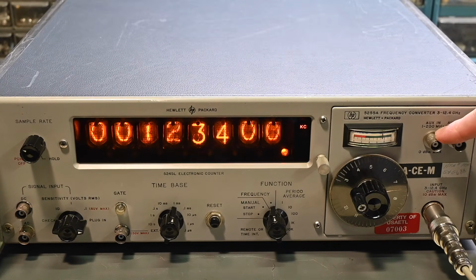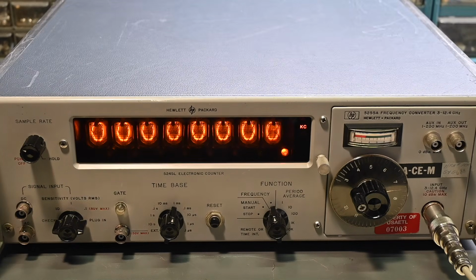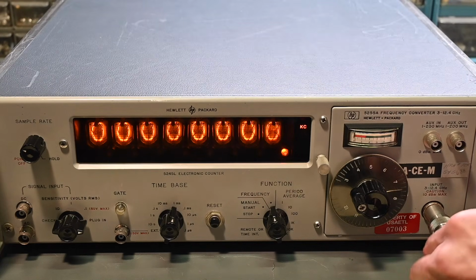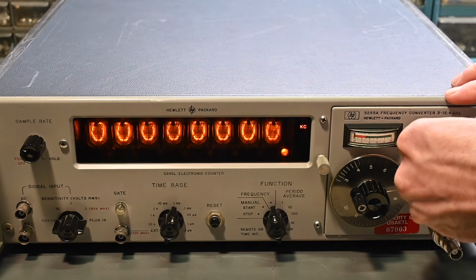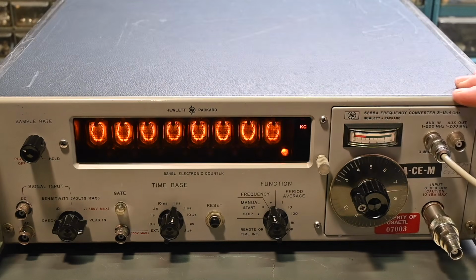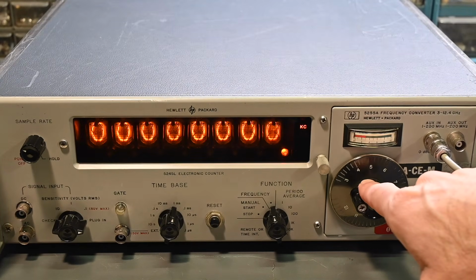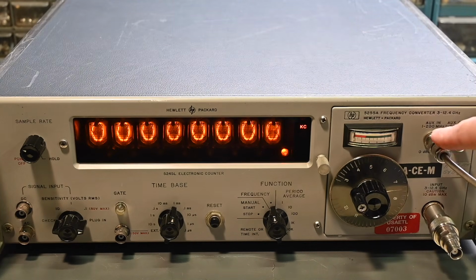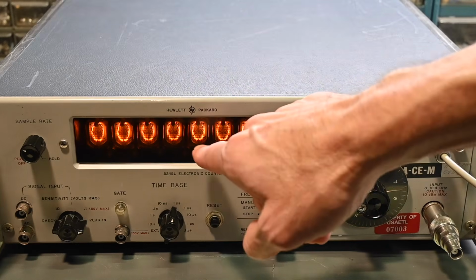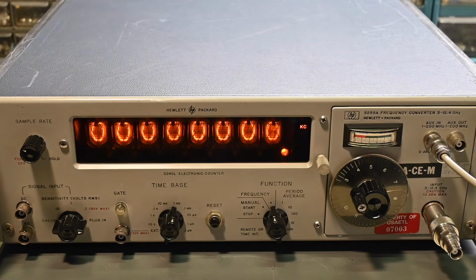So now let's try this prescaler input, so 1 to 200 megahertz. So turn the RF off. I'm just going to go over here, frequency 1 megahertz. Over here. So you can use one or the other input, but of course not both at the same time. And when you're using this input, then this dial has no purpose. So this is a direct reading. Whatever this frequency is, it's displayed directly over here. So I'll turn this back on again.